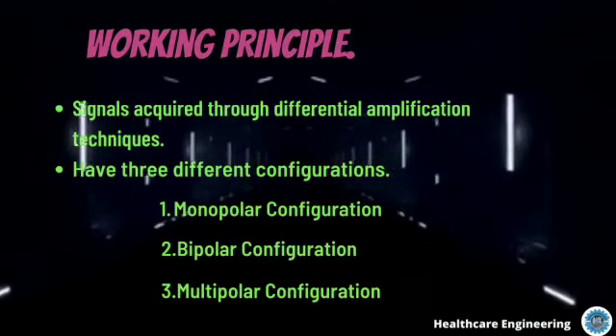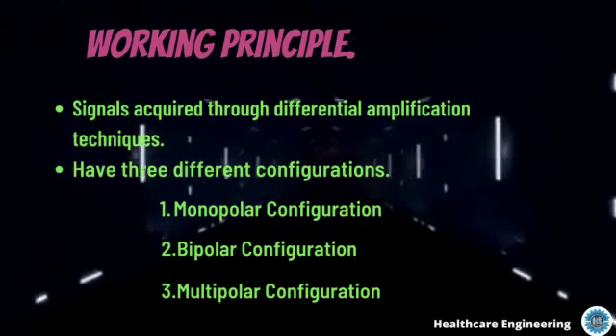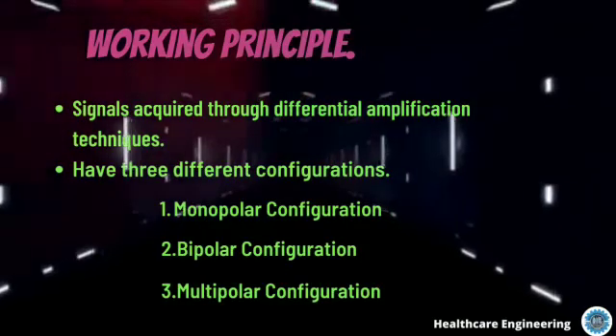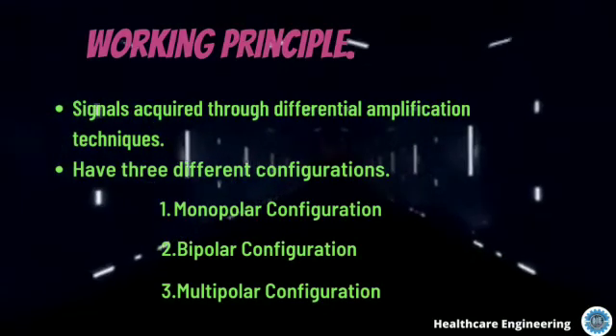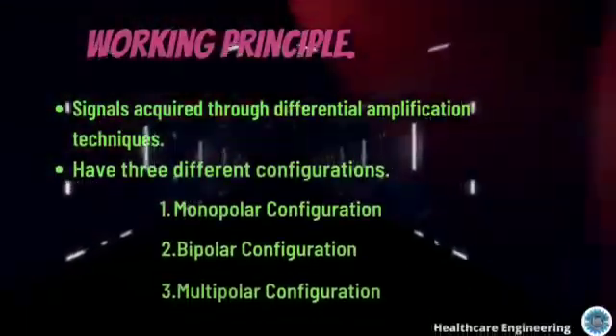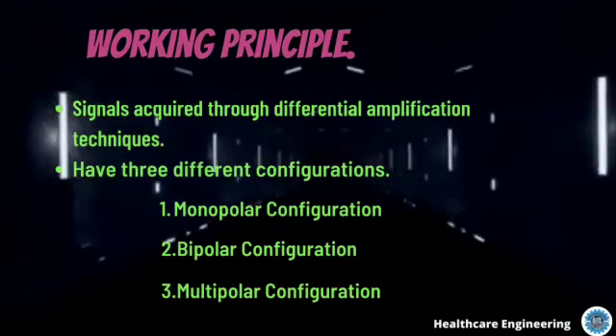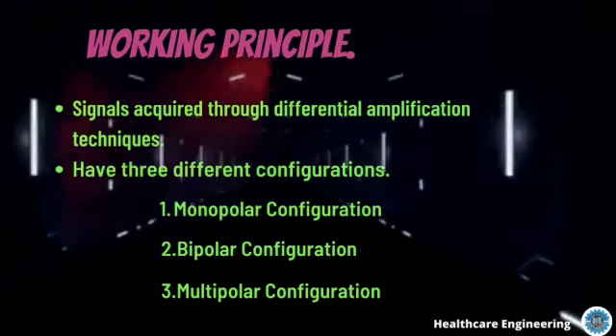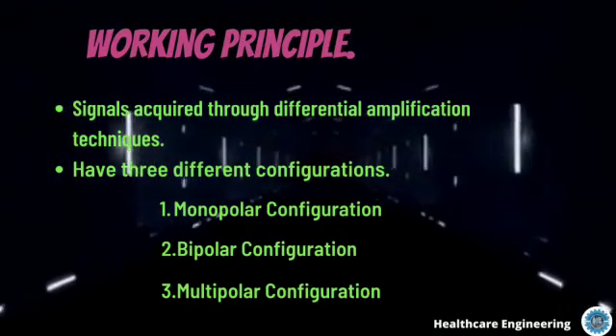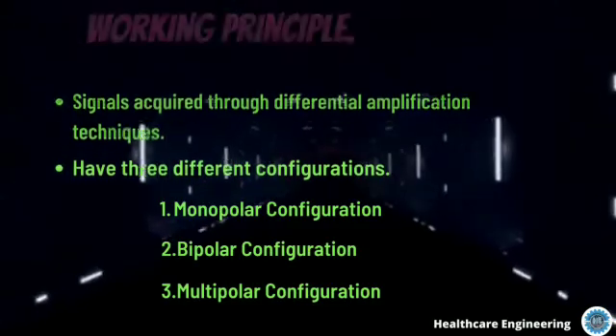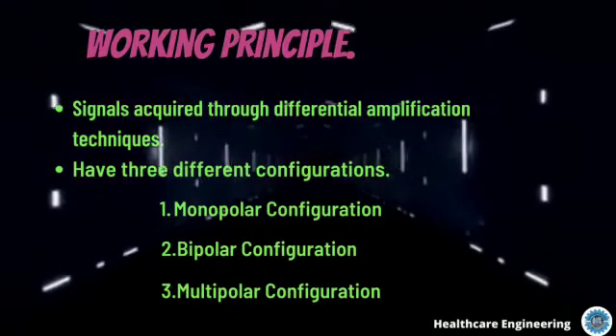Now let's talk about the working principles of EMG electrodes, starting with configurations. The EMG signal is acquired through differential amplification techniques. Differential amplifiers should have high input impedance and very low output impedance — ideally, infinite input and zero output impedance. The placement of the EMG detecting surface can be done through three different configurations: monopolar, bipolar, and multipolar configuration.